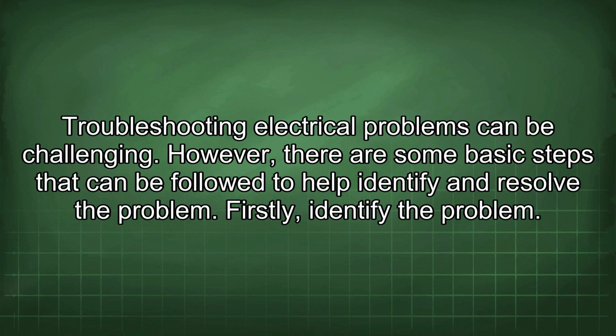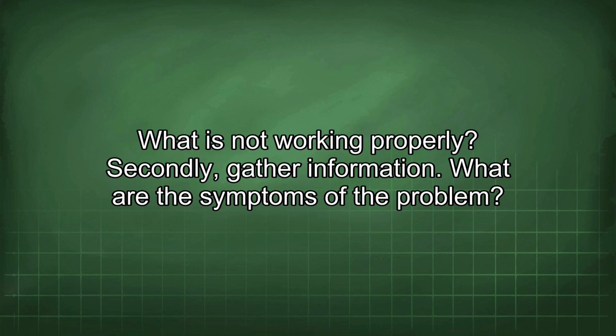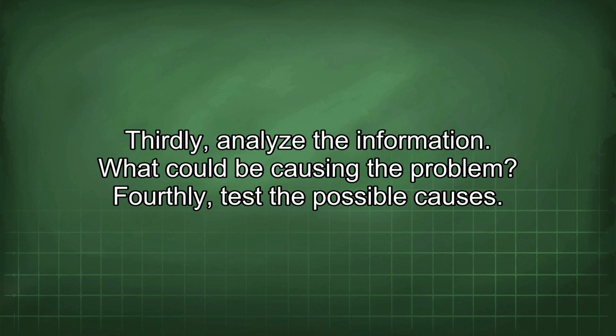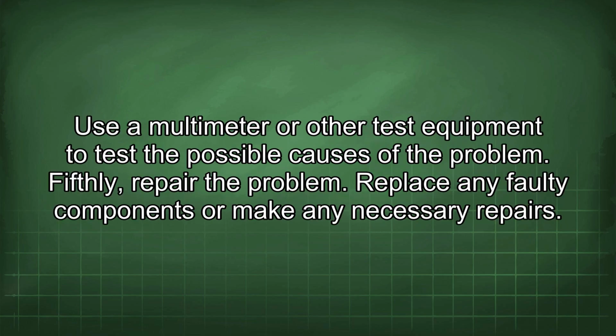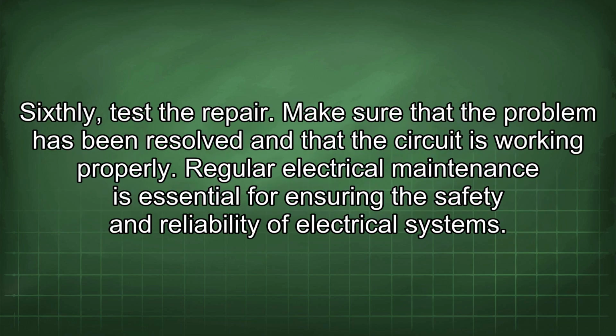Troubleshooting electrical problems can be challenging. However, there are some basic steps that can be followed to help identify and resolve the problem. Firstly, identify the problem. What is not working properly? Secondly, gather information. What are the symptoms of the problem? Thirdly, analyze the information. What could be causing the problem? Fourthly, test the possible causes. Use a multimeter or other test equipment to test the possible causes of the problem. Fifthly, repair the problem. Replace any faulty components or make any necessary repairs. Sixthly, test the repair. Make sure that the problem has been resolved and that the circuit is working properly.